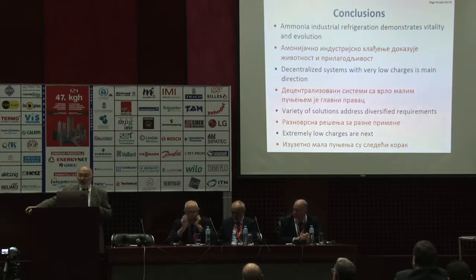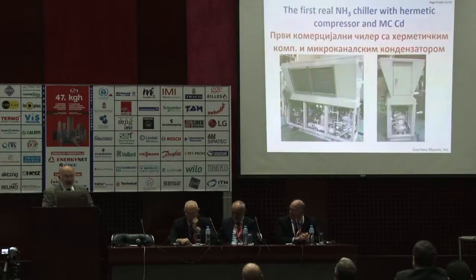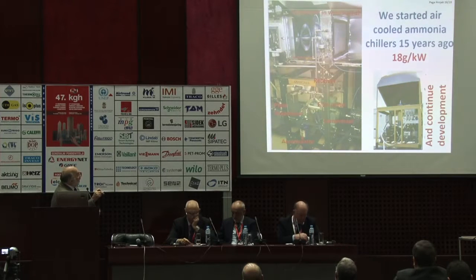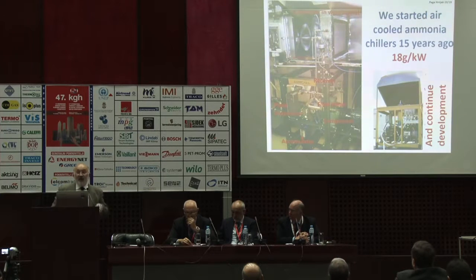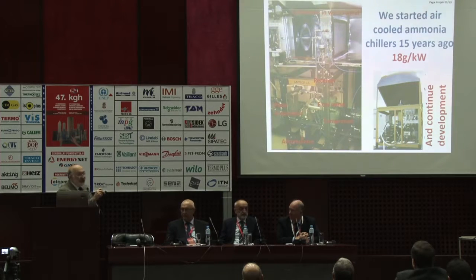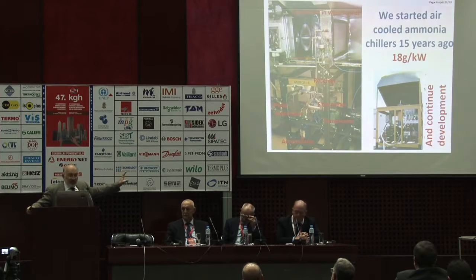And I believe that extremely low charges are the next step to go. How low is low? It is presented here. 18 grams per kilowatt was the charge of our first ammonia chiller that had 15 kilowatt capacity at normal conditions. Give me any fluid, give me any unit that has anything similar to 18 grams per kilowatt charge, I challenge you. Today we have 150 grams per kilowatt of propane or isobutane allowed, or that is what typically people see. We have made it for less than 50. But ammonia is a phenomenally good fluid for charge reduction for various reasons, primarily for the thermophysical properties of that fluid.